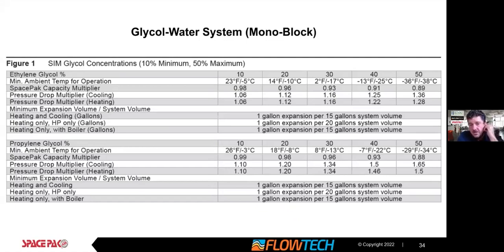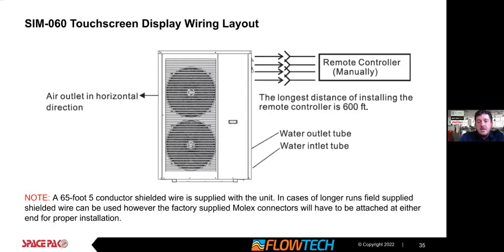We have people from all over the country here today on the presentation. So in our neck of the woods, we're using 15%, 20% glycol. Use what's local to your area based on your temperature. It's very important as well, not just for low ambient protection, but for protection of the equipment when you're in cooling mode. So the equipment's very sensitive to cold. So the glycol is essential. And if you're anticipating potentially getting any warranty, not that we've had those yet, but down the road, glycol is mandatory for system performance.